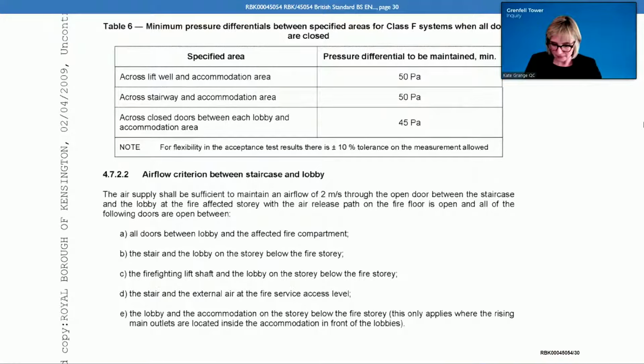You are referring to 2000. It is significant about the SCA guide. The 2012 version of the SCA guide had this standard as an acceptable standard. It got changed in the 2015 version, and changed again in the 2020 version. What I read to you earlier about needing to be a smoke control damper was recommended from the 2012 guide, not the 2015 one. In that guide, they go on to tell you what the acceptable standards are. That's just a generic introduction. I'm virtually certain of this.